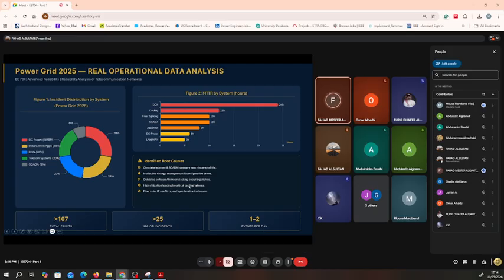For root cause analysis, we found obsolete telecom and SCADA hardware reaching end of life, ineffective change management, and configuration errors related to human error. We also found outdated software and firmware lacking security patches, and high utilization leading to critical cooling failures. Eventually we discovered root causes related to fiber cuts, IP conflicts, and synchronization issues.